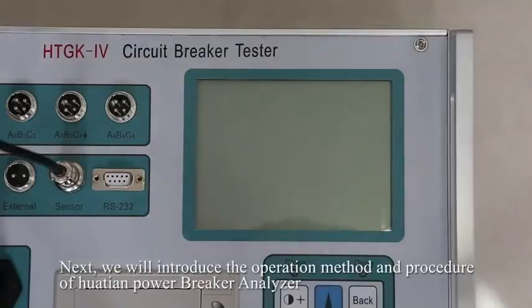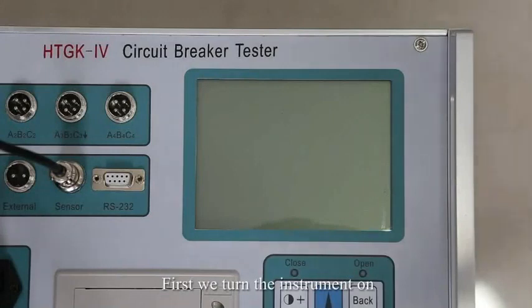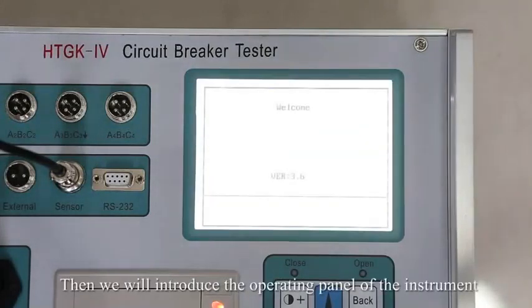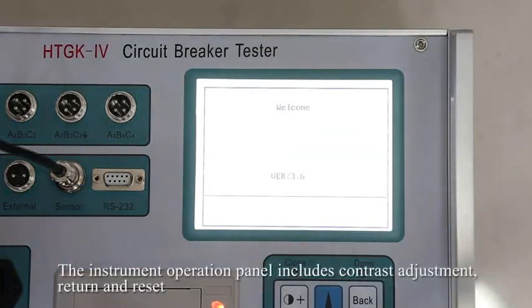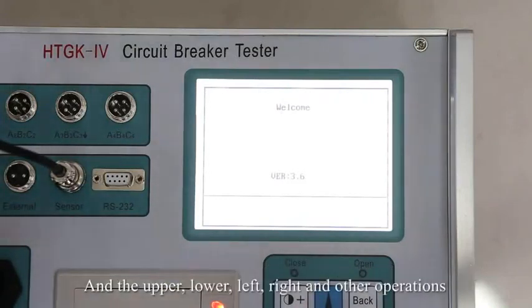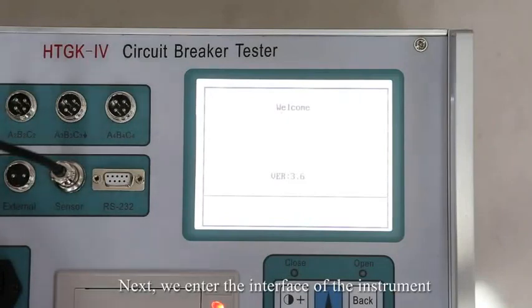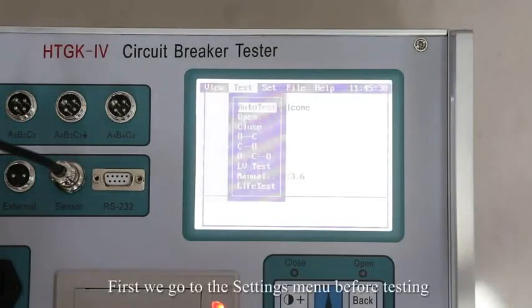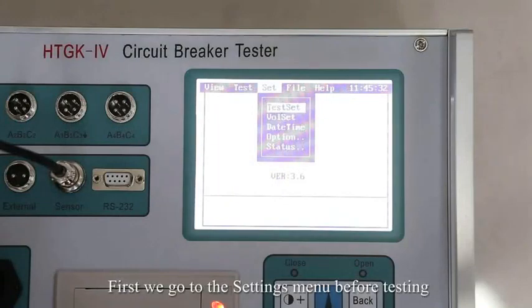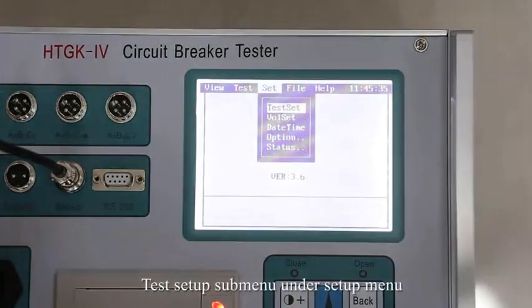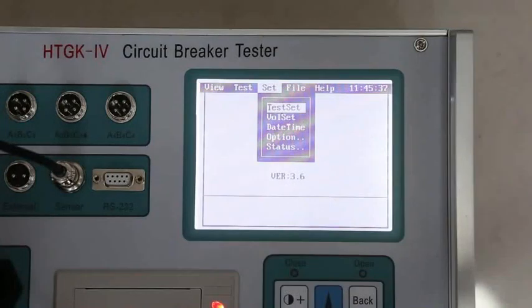Next, we will introduce the operation method and procedure of the Huatian Power Breaker Analyzer. First, we turn the instrument on. Then we will introduce the operating panel of the instrument. The instrument operation panel includes contrast adjustment, return and reset, and the up, down, left, right, and other operations. Next, we enter the interface of the instrument. First, we go to the settings menu before testing. Then the test setup sub-menu under the setup menu.